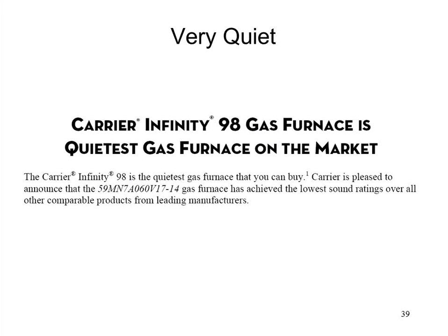If you put on a regular thermostat, which you can temporarily do, and I believe there's a jumper wire you got to cut to use a temporary regular thermostat in an emergency situation, it kind of disables all of the modulation sequences. So you really have to have the Infinity or Evolution stat for the modulating gas furnace to work correctly. And that's because we don't want to just know if there's a call for heat like a regular thermostat does. We want to know how much heat the thermostat wants.